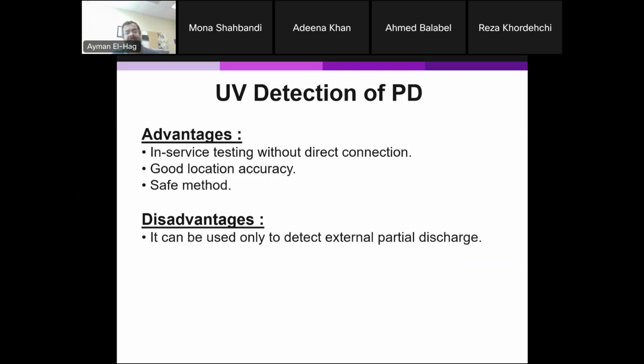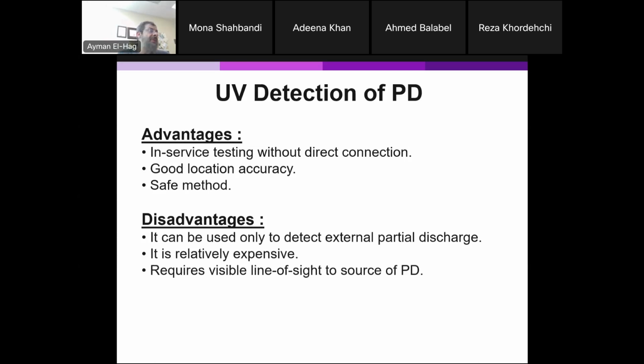Now, it has certain disadvantages as well. It can only be used for external discharges. So, for example, if there's an internal defect in the ceramic insulators or the polymer insulators, you won't be able to see anything. It has to be something external so that you can see it. As I mentioned, this is one of the most expensive. The camera is a few tens of thousands of dollars, 30, 40,000 if you want a good corona camera. Of course, you also have to have a line of sight. If there's an obstacle, you won't be able to see anything.